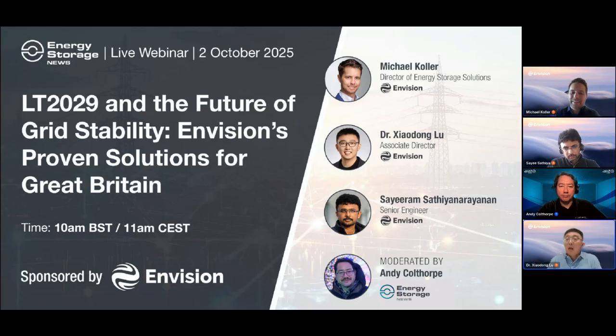Yeah, thanks, Michael. Yes, we provide the overload capability at two levels. At unit level, we provide the overload capability to make sure the current limit is not easily triggered, because we are a voltage source. If we trigger the current limit, the control function would be limited. And we also provide the overload capability at the plant level. Plant level means we make sure our short circuit level and the inertia response meet the requirement of the system operator.